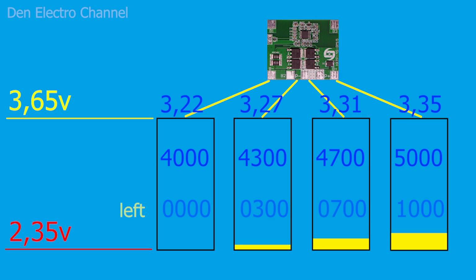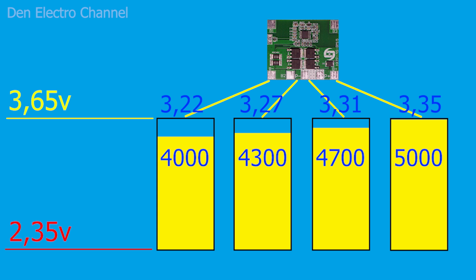When charging starts, the battery with the most capacity will be charged first. It will reach 3.65 volts and the BMS will stop charging, leaving the remaining banks undercharged. Therefore, in this system, it is necessary to use batteries with the same capacity and the same charge level, otherwise it will be complete chaos.